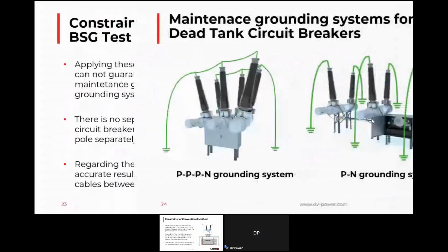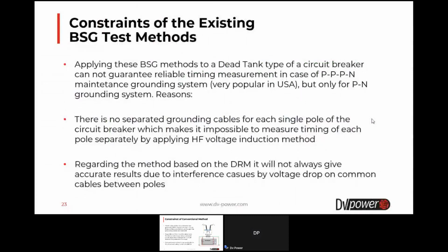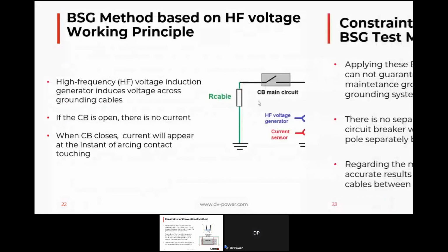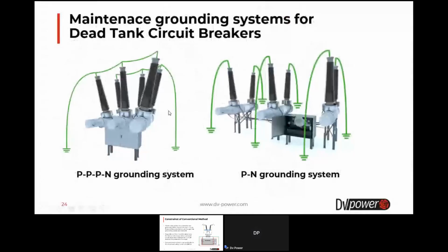So there are two reasons why these methods are not applicable or reliable in the case of the PPN grounding system. There are no separate grounding cables for each single pole of the circuit breaker, which makes it impossible to measure the timing of each pole separately by applying the high frequency voltage induction method. As you can see in this slide, the high frequency induction method can be applied for the PN grounding system, since there are separate grounding cables for each pole, but it cannot be applied for the PPN grounding system because there are no separate grounding cables for each pole.